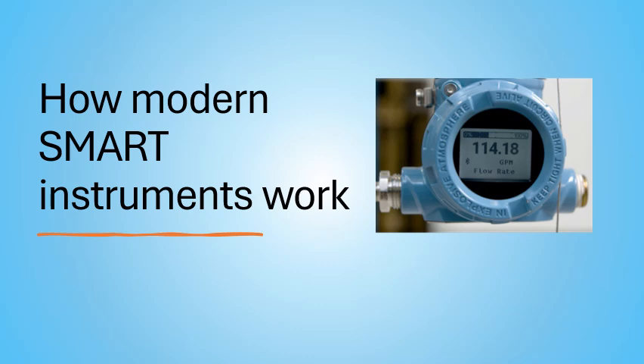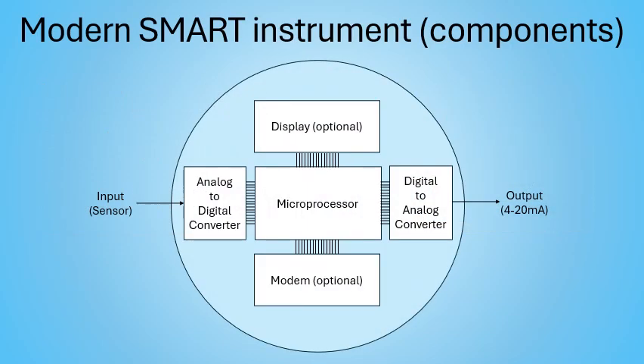Okay, so how do the modern smart instruments work? Let's talk about that. The key components of a modern smart instrument: you have your input, that'd be a sensor, thermocouple, RTD, might be a pressure sensor, a little piezo disc, might be a capacitive element in a DP transmitter, but there's some electrical parameter that's going to be measured, and then that is sent to the analog to digital converter. That is going to send, you can see all these bits here, there should be 16 bits on a typical instrument going into the microprocessor.